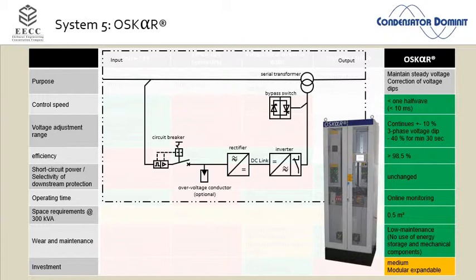Now, that was the idea from the beginning. Why did we want to have a system like this? The only thing we add into the system between input and output is this transformer with a low impedance, so that we keep the short circuit current, the short circuit power, as high as possible. The impact on the short circuit power is very low. The second is, during normal operation, when there's no voltage sag, I'm running very little energy through my power electronics. There's a little bit of freewheeling current that also goes to the power electronics, but nothing compared to a UPS.